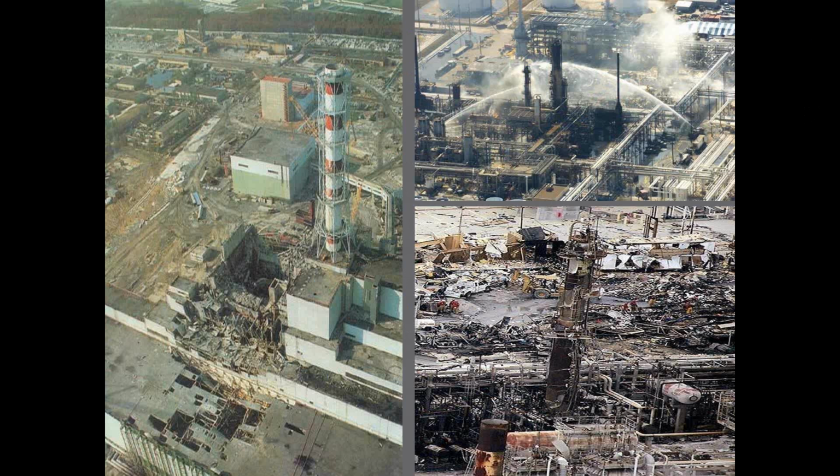So one day they decided we better do our PMs on the rods. The way you do this PM is you close the rods all the way and confirm that they close. You open the rods all the way, confirm that they go to wide open, and then you go back into control. Well, on this particular day, they closed the rods all the way. When they drove the rods to 100% open, the rods stuck at 100% open.